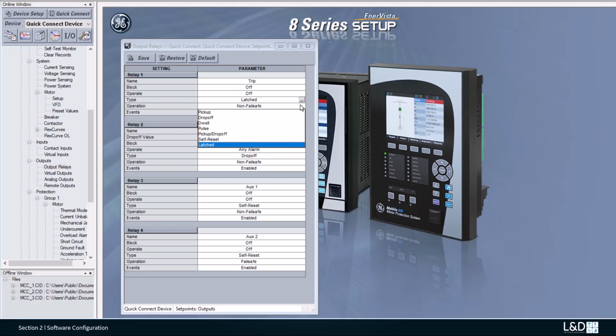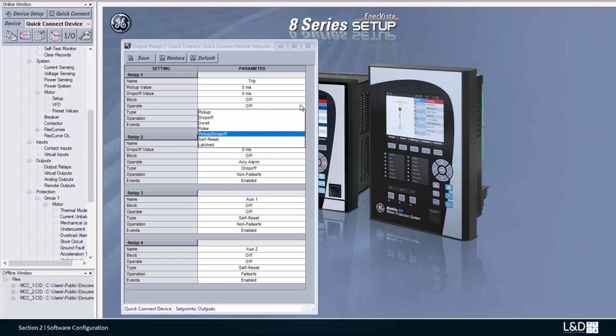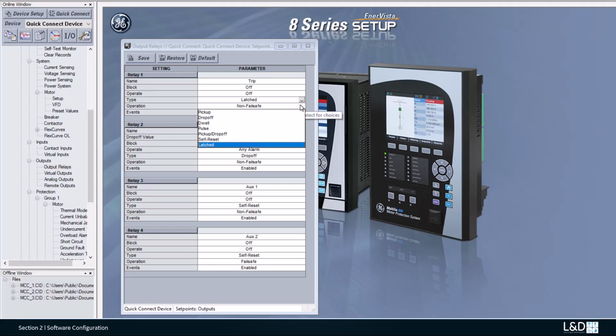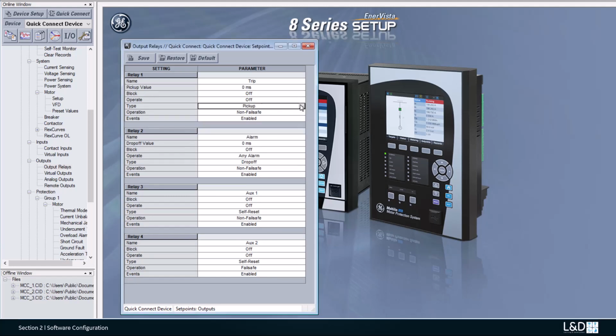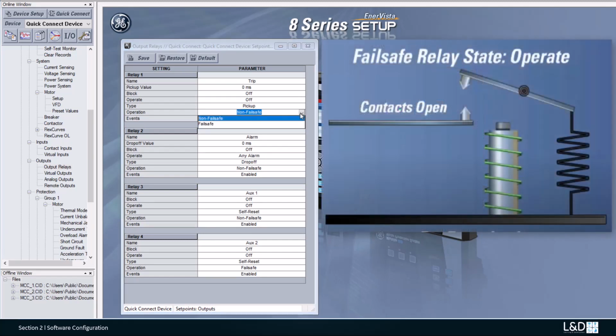Depending on which option you choose, some settings will disappear or be added. For example, when you choose pickup and dropout, you will have the pickup and dropout values available for you to enter. And when you're using self reset and latched, the delay time will disappear. Okay, so this is the type, and under the options you have fail-safe and non-fail-safe. Same as the 369, the fail-safe relay operates when the coil is de-energized or the relay control power is lost.